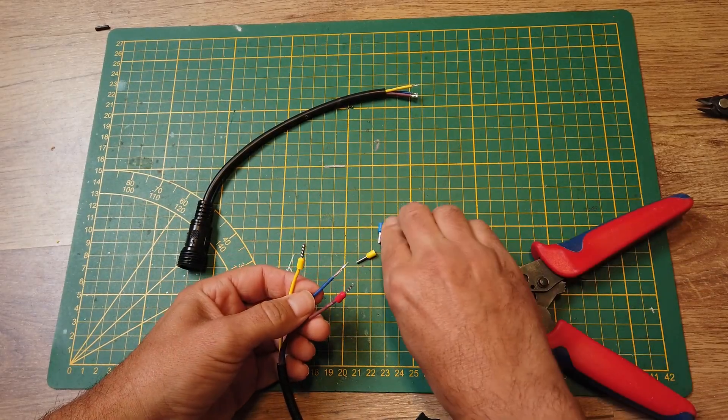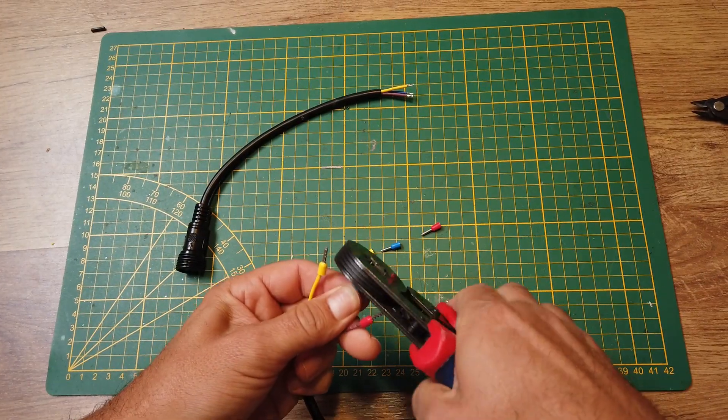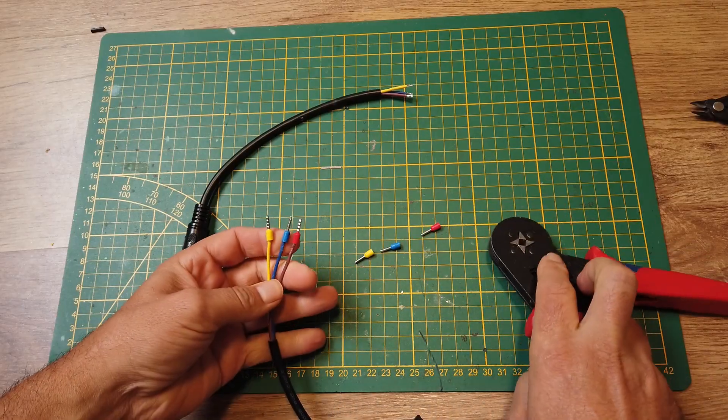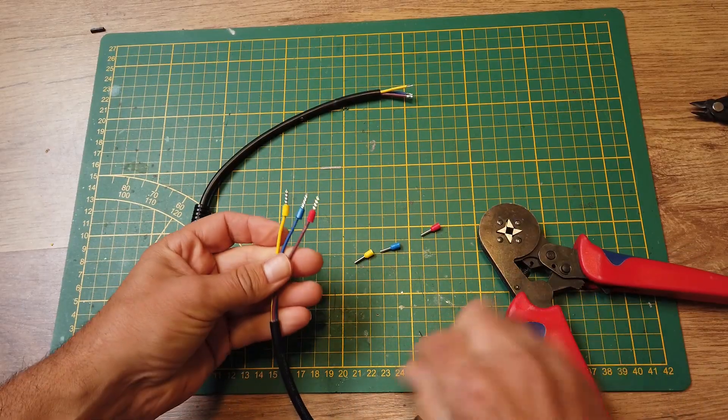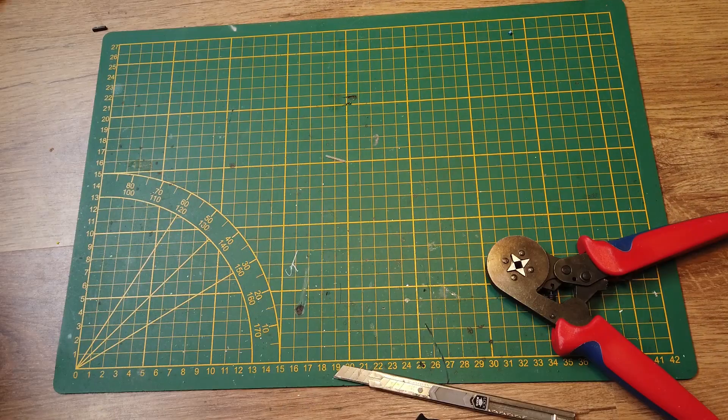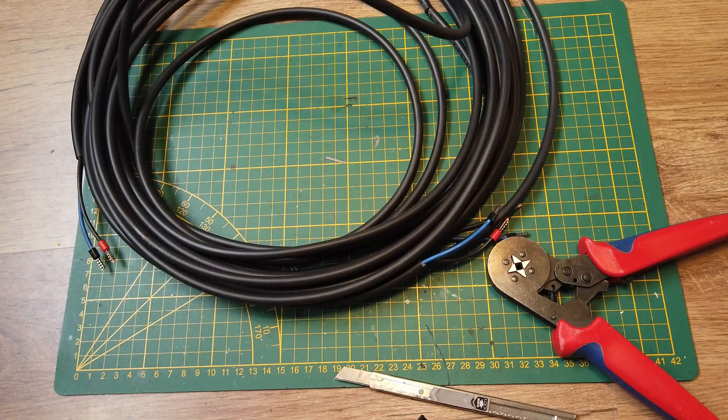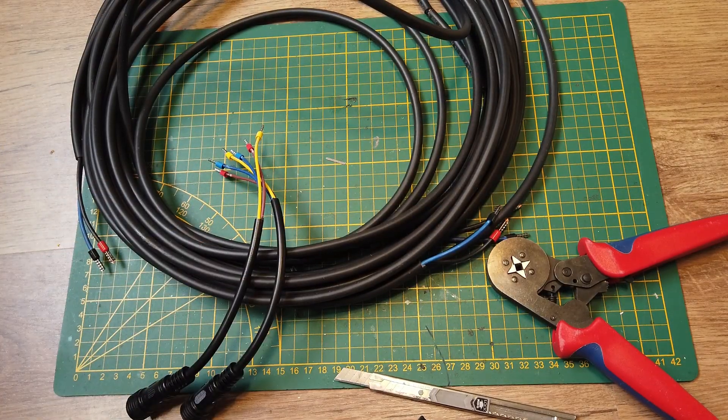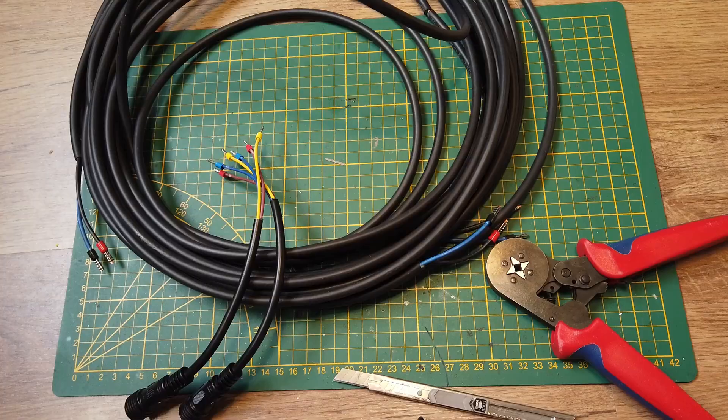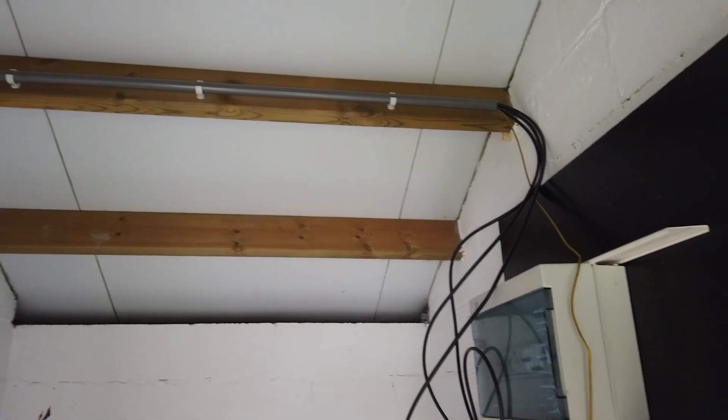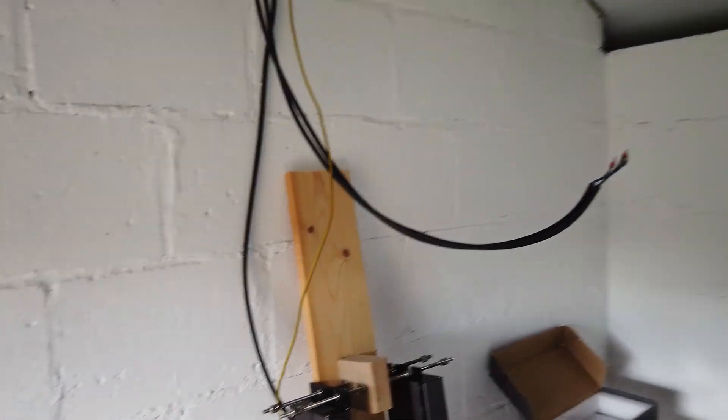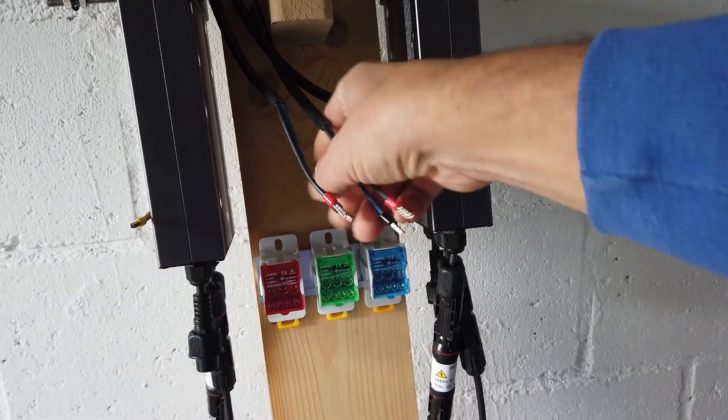While I was busy, I prepared cables between the same DIN rail connector and the 220 volt breaker box. Had some spare 2.5 square millimeter cable. Of course that's overkill as current per cable will not exceed 4 amps. These cables, together with a ground wire, are mounted in a PVC tube on a support beam of the shed.